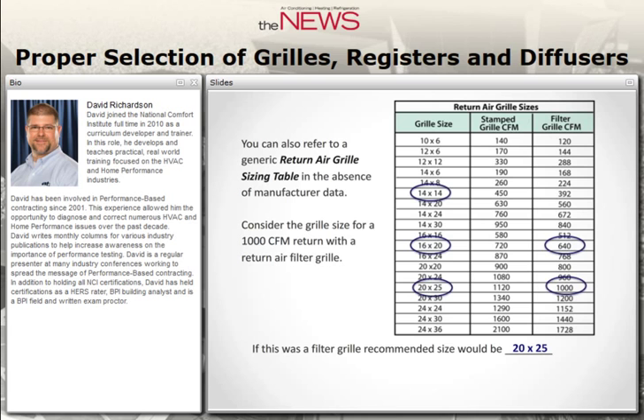Properly sizing filter grills also helps your filters work better. A lot of times filters fail to do what they're designed for because air speed going through the grill is so fast that dirt just gets pulled right through it. If you want to use more restrictive filtering media such as pleated filters, make the filter grills oversized. Air takes a path of least resistance — if it can't go through a filter, it will go around it.